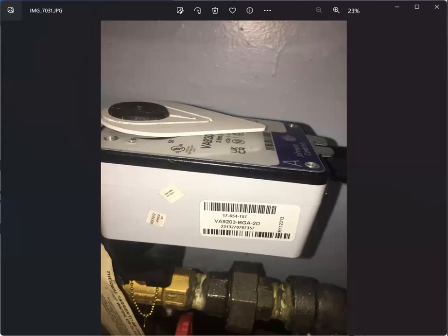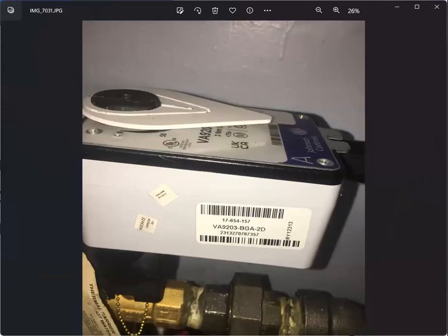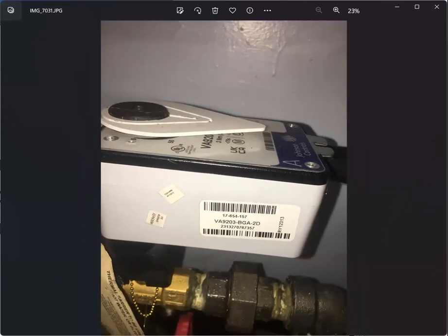And the control panel, you need to identify it also, the model number, and take note of it because you're gonna need it when you're evaluating the specs in the drawing or the approved submittals, the approved documentations.